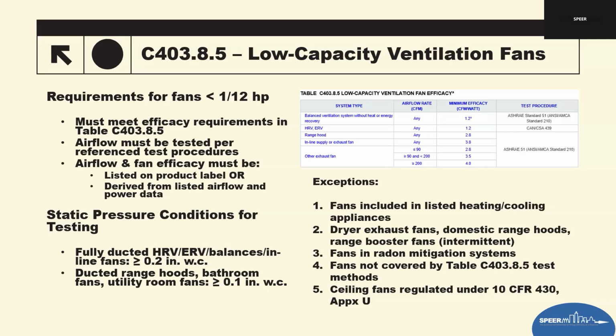Field inspection, verify equipment label matches submitted performance. So what they did in plan review is actually what they installed. Check ducting is installed so static pressure approximates tested conditions. In other words, verify that the duct is not compromised, crushed, kinked, sharp bends, things that are going to raise that static pressure and lower airflow. And then ensure no prohibited fans are used in ventilation applications.